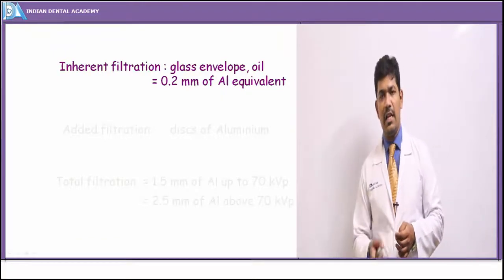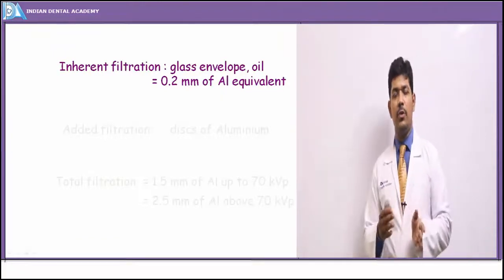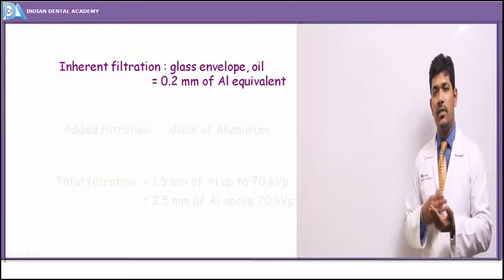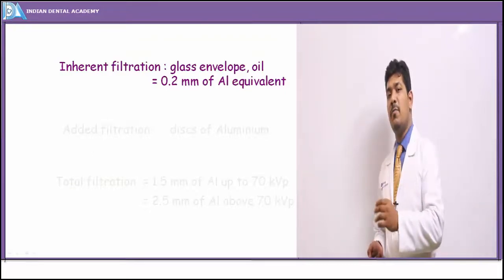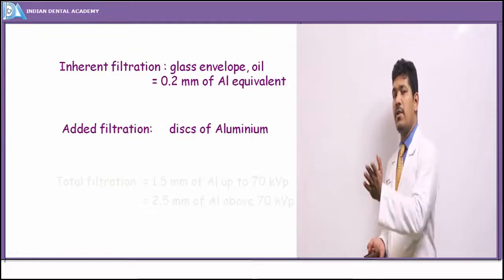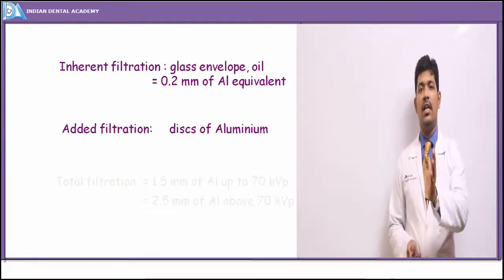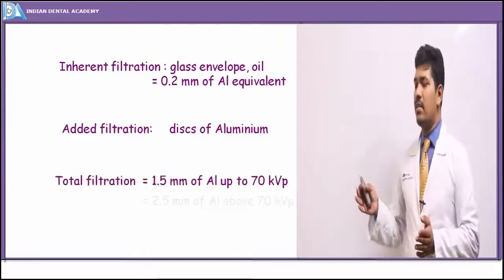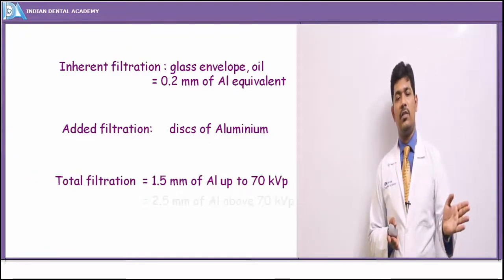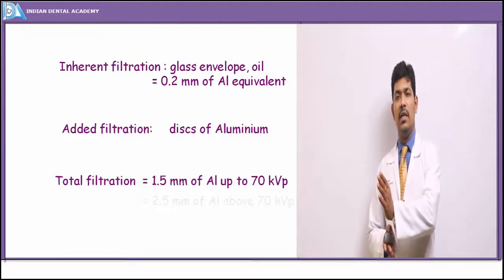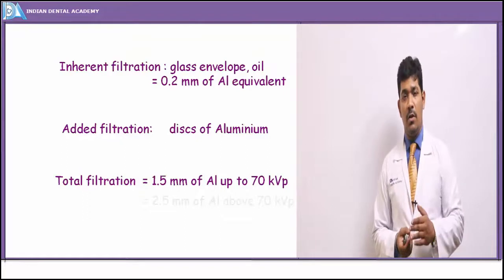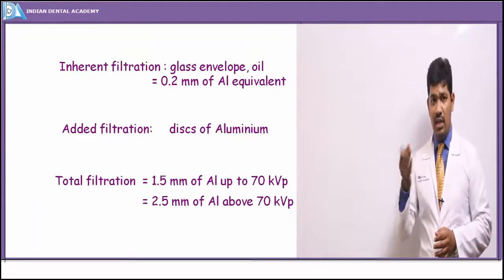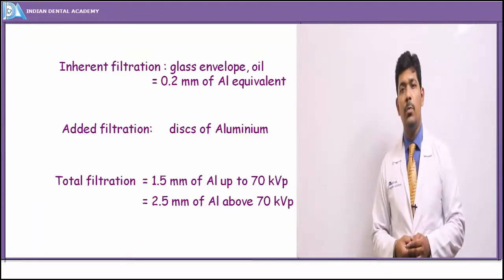Filtration within and outside the x-ray tube is divided into inherent filtration — provided by the glass envelope and insulating oil, equivalent to 0.2 mm of aluminium — and added filtration via an aluminium disc. For intraoral x-ray units operating at around 70 kVp, 1.5 mm of aluminium is used, while for cephalometric and tomographic units operating above 70 kVp (up to 100 kVp), a 2.5 mm aluminium disc is used.